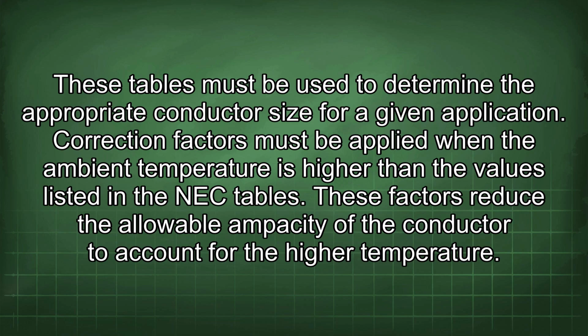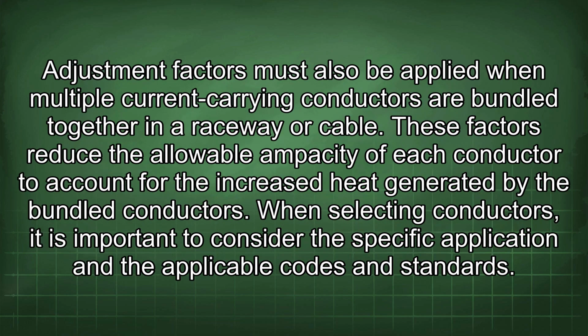Correction factors must be applied when the ambient temperature is higher than the values listed in the NEC tables. These factors reduce the allowable ampacity of the conductor to account for the higher temperature. Adjustment factors must also be applied when multiple current-carrying conductors are bundled together in a raceway or cable. These factors reduce the allowable ampacity of each conductor to account for the increased heat generated by the bundled conductors.